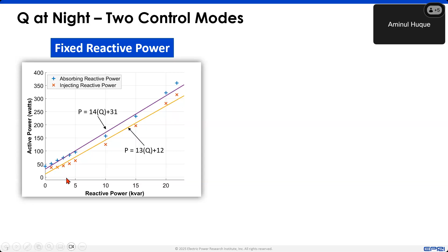So that's one type of voltage control function where some other entity may issue a command to the plant: hey, give me this much var until I provide you the next command. But what if you want the plant or inverter to operate autonomously? You can load a volt-var curve. That's what is shown in the inset figure on the right side. We provided a volt-var curve, which is, I think, a modified version of the IEEE 1547 category B volt-var curve, not the default one. And basically, we then use a grid simulator to change the voltage, go from low voltage to high voltage, and then bring the voltage back to low voltage. And for each, we took a continuous recording of the reactive power absorption in response to the voltage variation. That's the plot you are seeing on the right side.